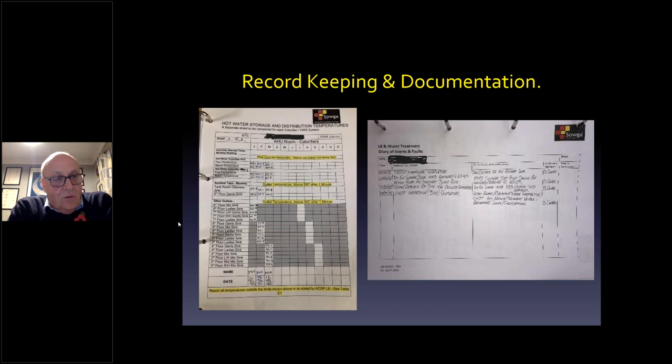Going on to water features, they're normally covered in section 3 of the HSG 274. Again, it all depends whether your water feature has got fish in it. If it has, you don't want to be putting any biocide treatments into that, as it will kill the fish off. Off the top of my head, I can't really think what you would do in that circumstance. The water features that we've maintained in courtyards have a biocide put into the system, and that is checked on a regular basis. We normally do that through a contractor because it is specialised maintenance, but they will have a biocide going through there to prevent any type of bacteria growing as well.